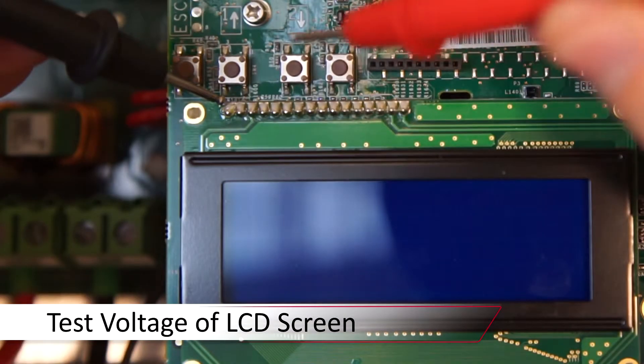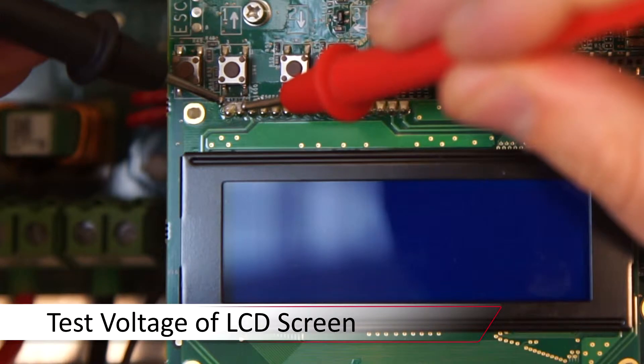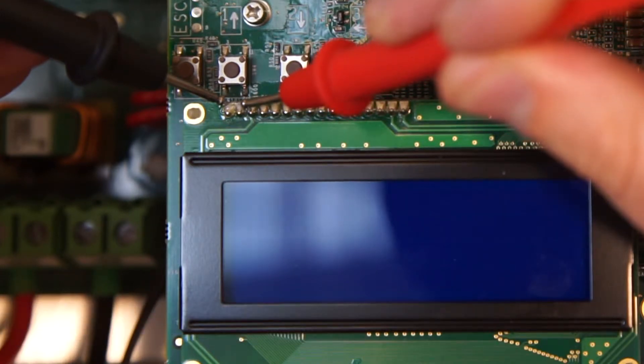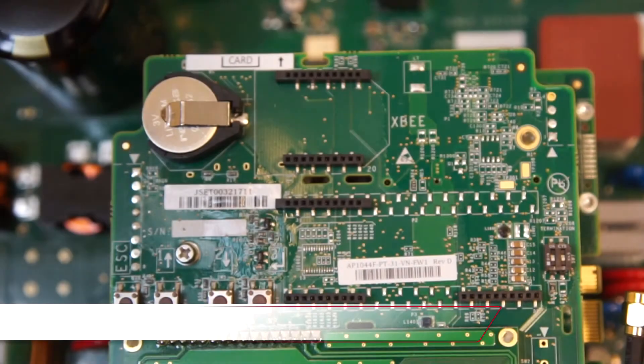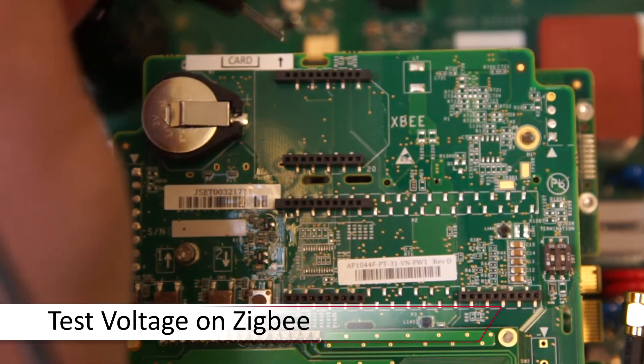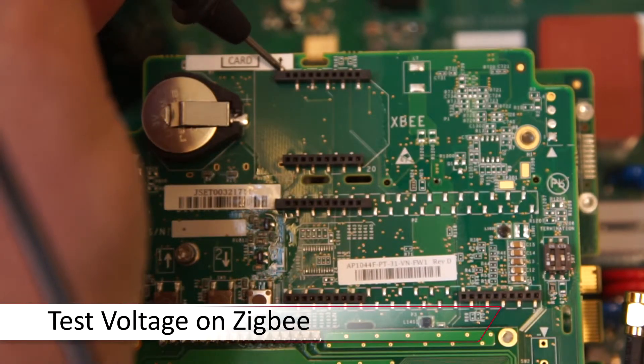Once the system is energized with the AC on, take a DC measurement off the first two solder points directly above the LCD screen. We expect 5 volts DC. To test the Zigbee interface, measure DC voltage on the upper left and bottom right solder points above and below the 10-pin connector.